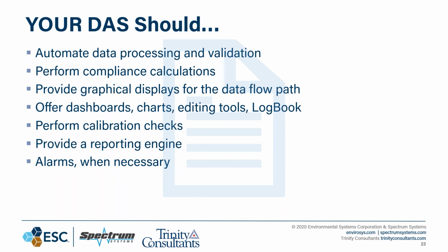Oftentimes I go to the facilities and I ask, okay, where's your DAS? Oh, it's out in the CEMS shack. Okay, where's the screen? Well, we have to go out to the CEMS shack to look at it. Well, where are you getting the alarms? Well, the alarms are being annunciated back to the main DCS. And the problem with that typically is that the main DCS could look like a Christmas tree with a lot of unacknowledged or yellow blinking alarms that have operational alarms that might not mean too much to you at the time. And your CEMS alarm is buried in those alarms. So it's always helpful to have these dashboards and have all your permit requirements built out so that it's blinking real bright and red at you saying, hey, look, if you don't pay attention to me, we're going to have an exceedance.